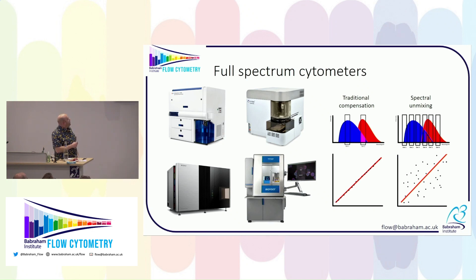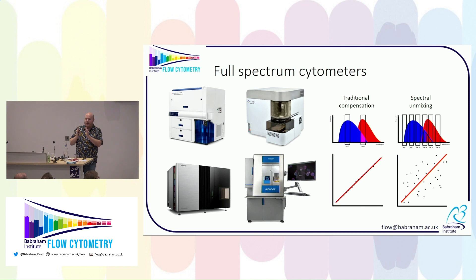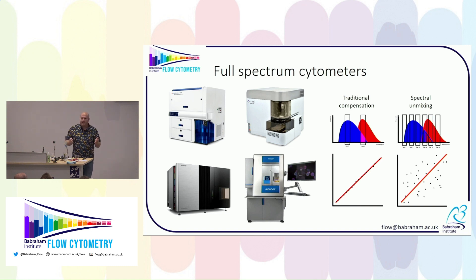We have four machines: the BD A5SE, the Aurora, the ID-7000, and the Bigfoot — these are our full spectrum machines. But none of them are really full spectrum in the way that I would think about it. They look at entire spectrums from the laser line to about 800 nanometers, but they all partition their spectra differently. Some are 40 nanometer, some are 5 nanometer bandpasses or graded PMTs. It's still spectral because of the unmixing algorithms rather than the actual instrumentation itself.